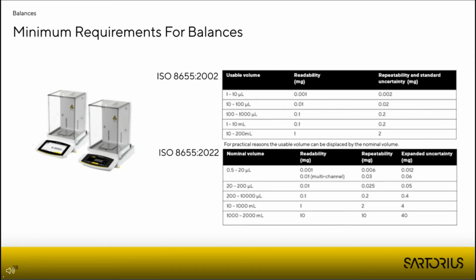And one additional important change is that the new ISO allows, when calibrating a multi-channel pipette of 20 microliter on a multi-channel balance, to use an analytical balance. So when using a multi-channel balance, a semi-micro balance is not needed; it's okay to use an analytical balance. And this, of course, is very useful as there are no multi-channel semi-micro balances on the market yet.